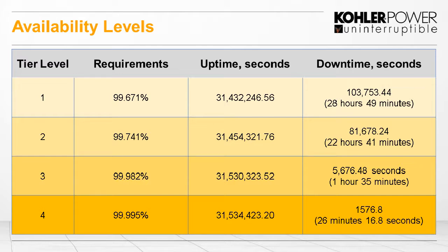Now, that doesn't seem much difference in those percentages, just a couple of points of a percent. But if you look on the right, that availability translates to a downtime of nearly 29 hours on average a year for a tier level 1, dropping quite dramatically to 26 minutes for tier level 4. So any small change in that percentage will make a big difference in the downtime.